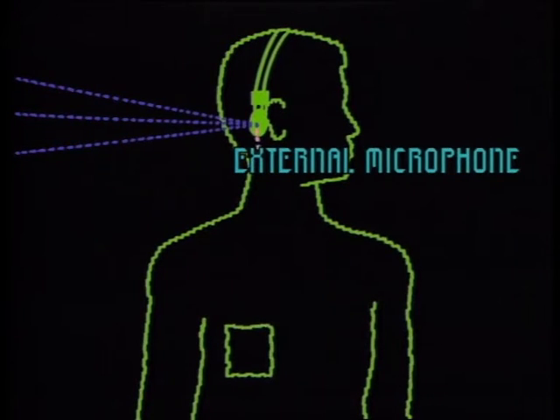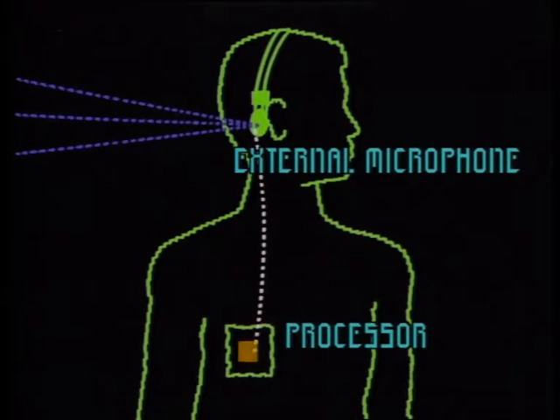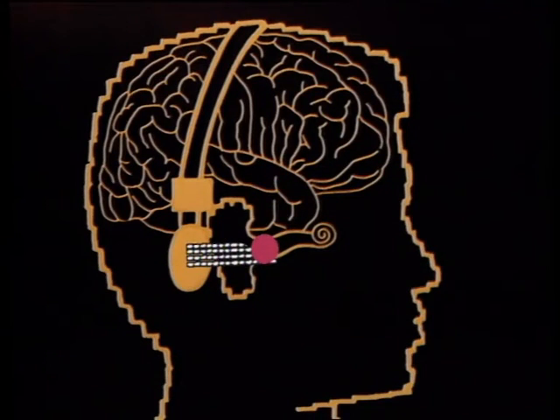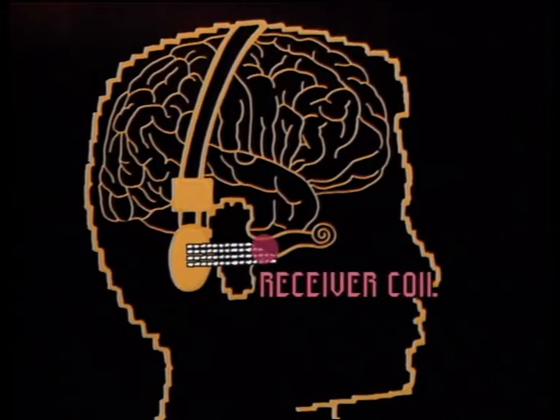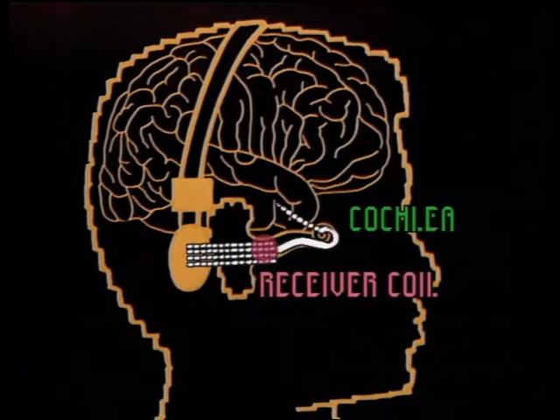The external microphone at the back of the patient's ear picks up sounds and transmits them by wire to the processor. The processor is set to the specific requirements of each patient, and encodes those signals before sending them back up to the ear. The messages are transmitted into the ear through the skin, where they are decoded by a receiver coil and sent into the cochlea. From there, they travel to the brain as sound.